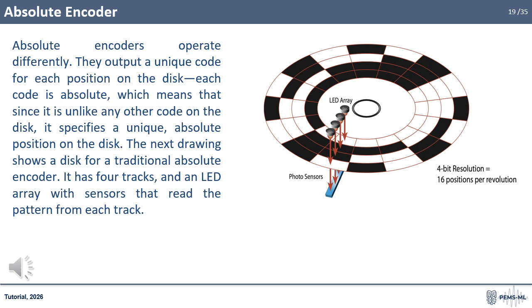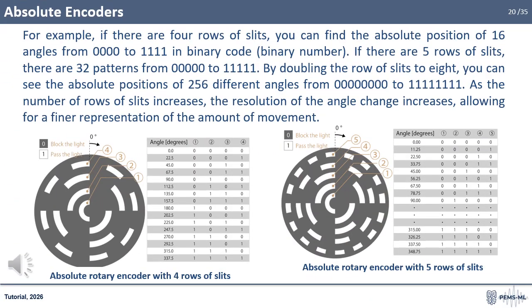Absolute encoders operate differently. They output a unique code for each position on the disk. Each code is absolute, which means that since it is unlike any other code on the disk, it specifies a unique absolute position on the disk. The next drawing shows a disk for a traditional absolute encoder. It has 4 tracks and an LED array with sensors that read the pattern from each track. The incremental method has only 1 row of slits, while the absolute method has multiple rows.